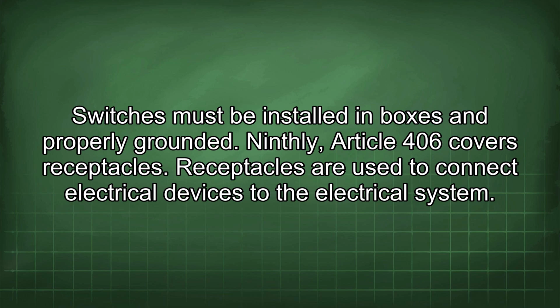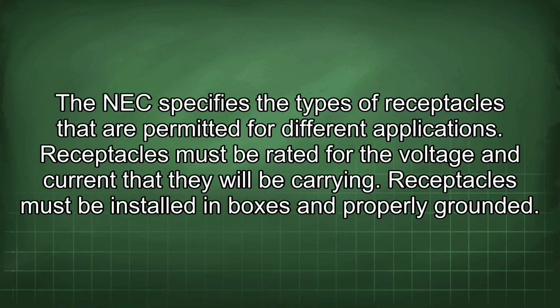Ninthly, Article 406 covers receptacles. Receptacles are used to connect electrical devices to the electrical system. The NEC specifies the types of receptacles that are permitted for different applications. Receptacles must be rated for the voltage and current that they will be carrying. Receptacles must be installed in boxes and properly grounded.